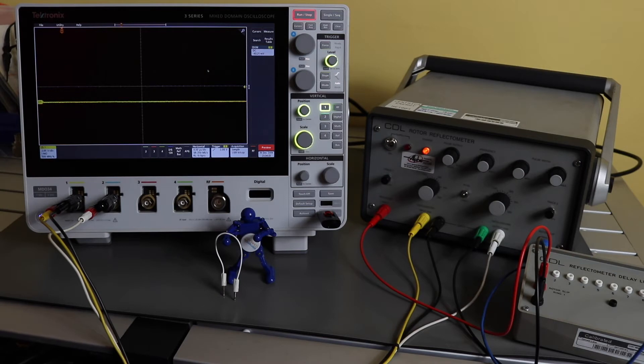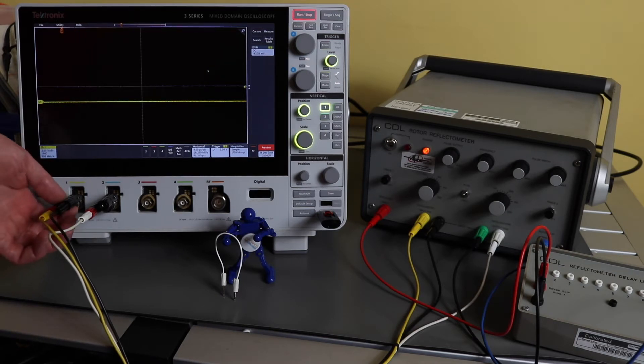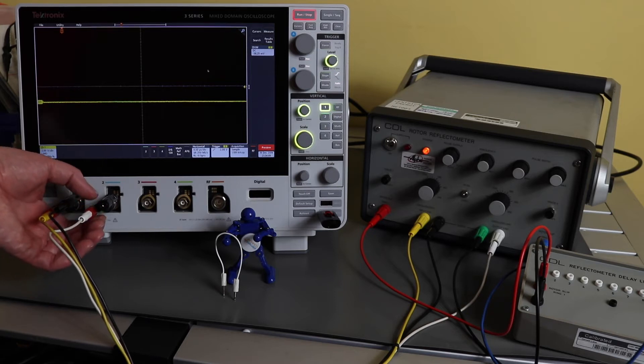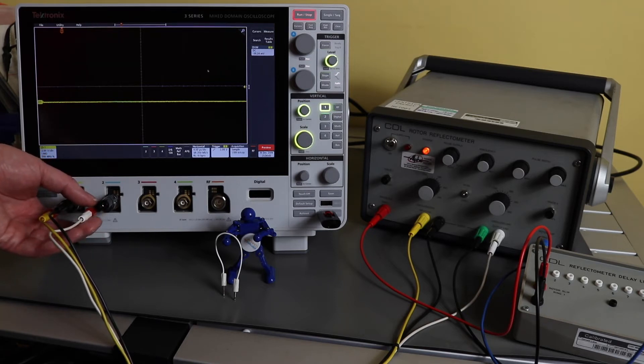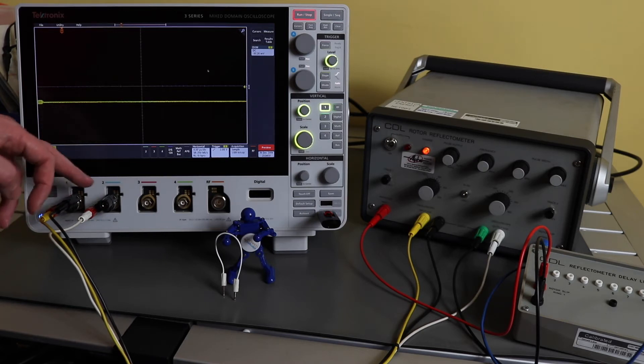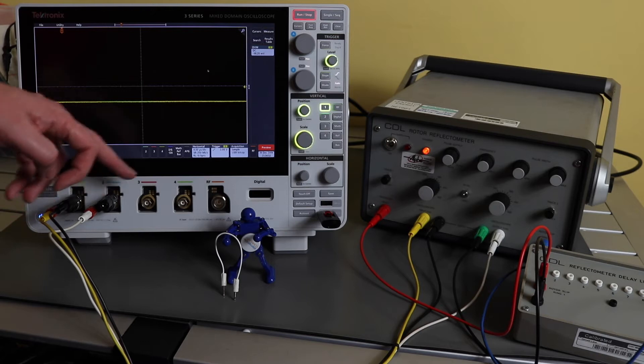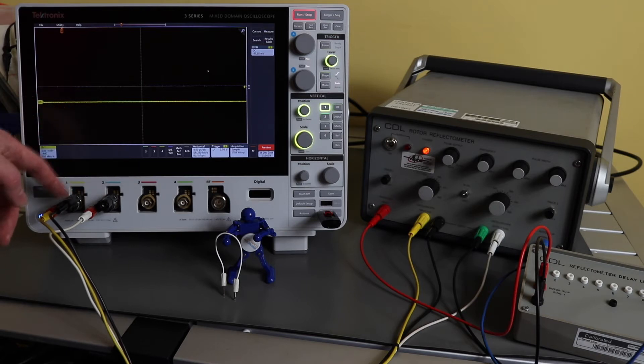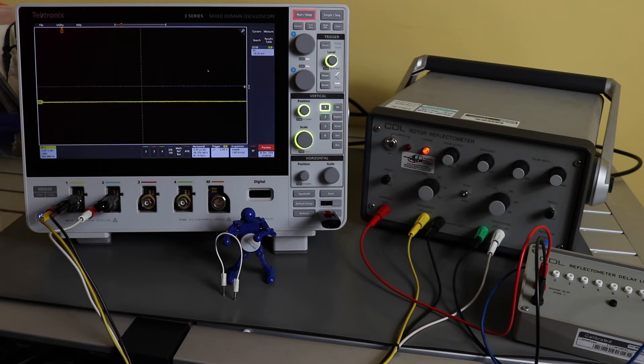This is a single-channel rotary reflectometer, so I have both double transit traces coming back on channel 1 and then the single transit trace on channel 2. More modern reflectometers actually have dual channel output, so I would be using three channels in that case because the double transit signal will be split across two channels.